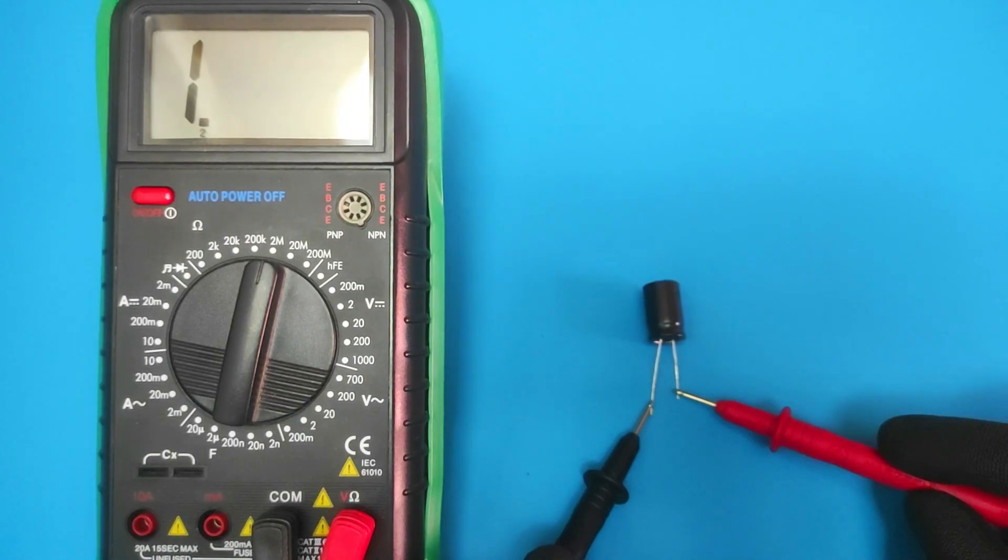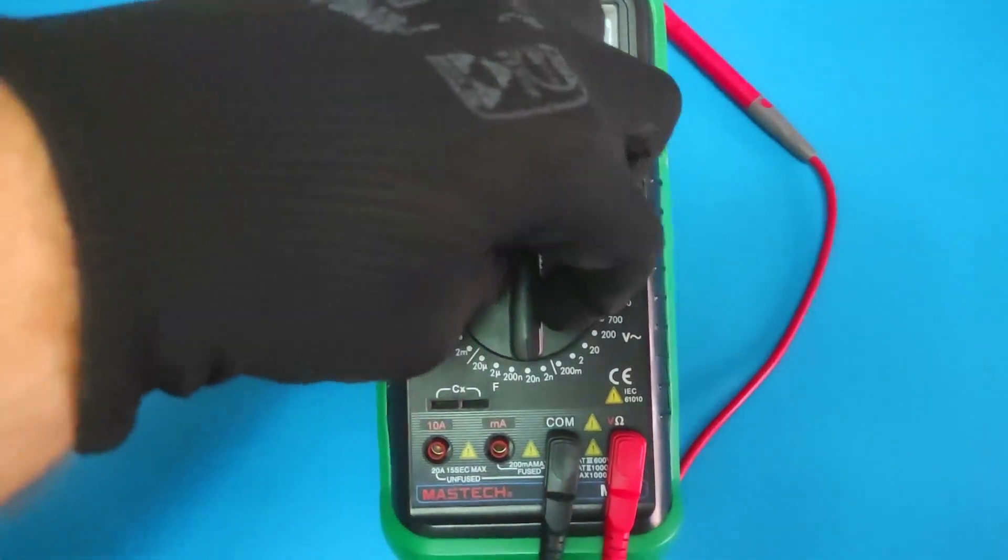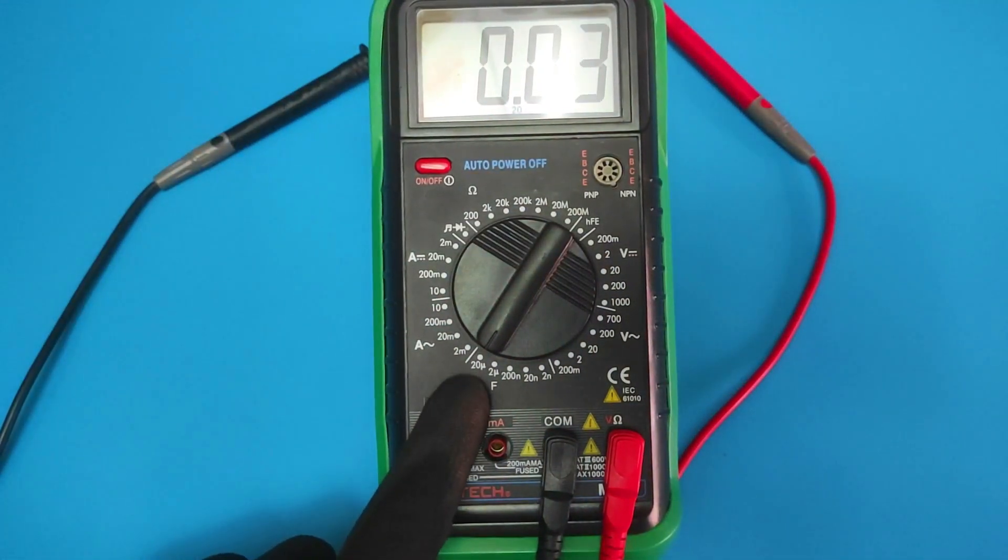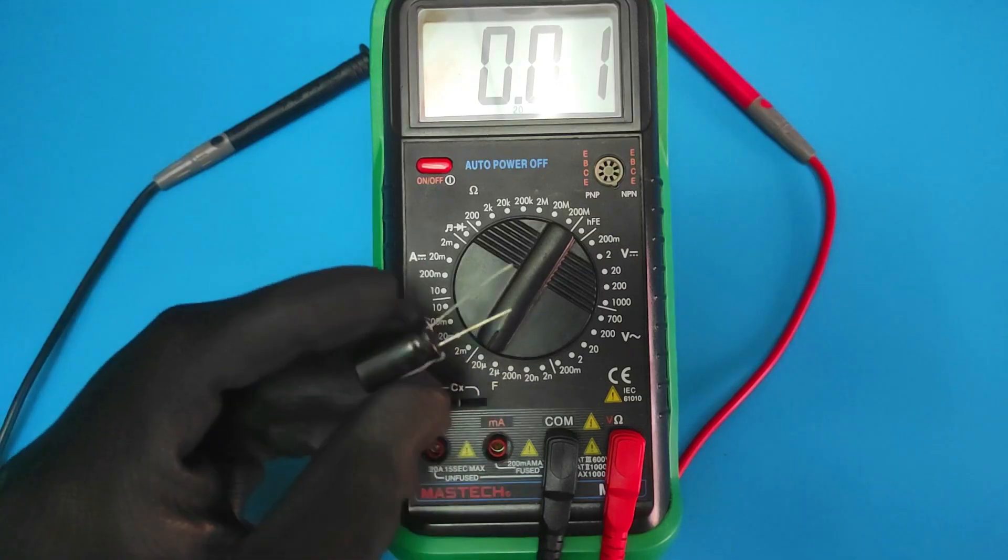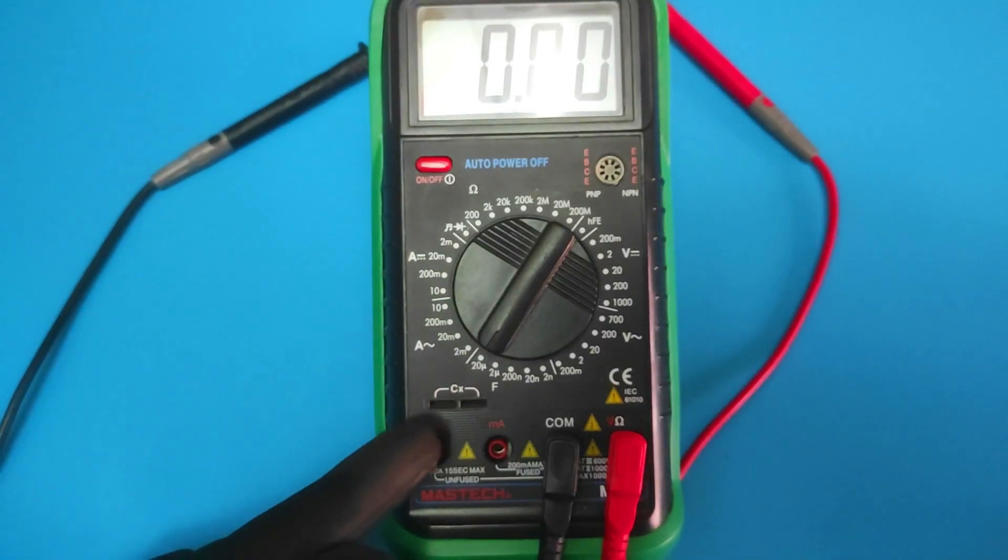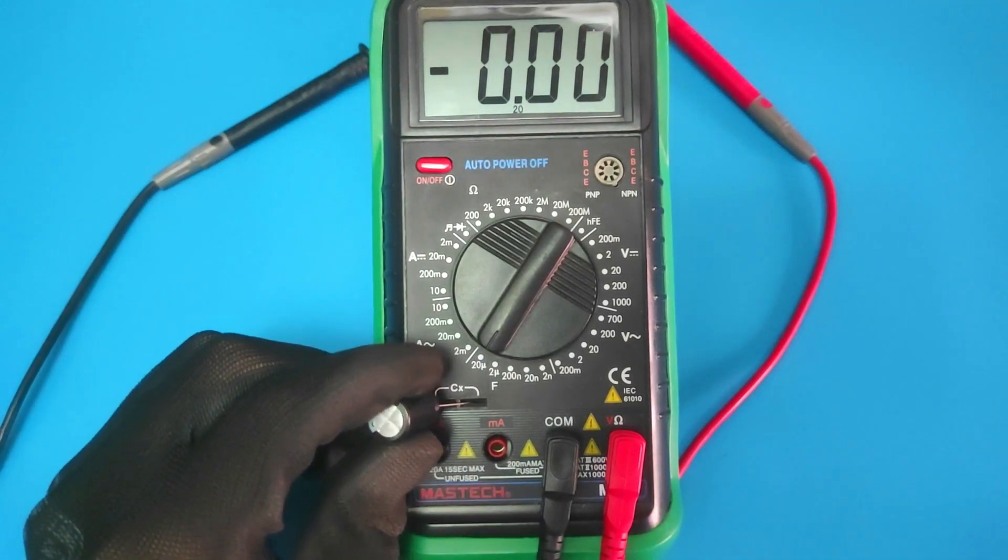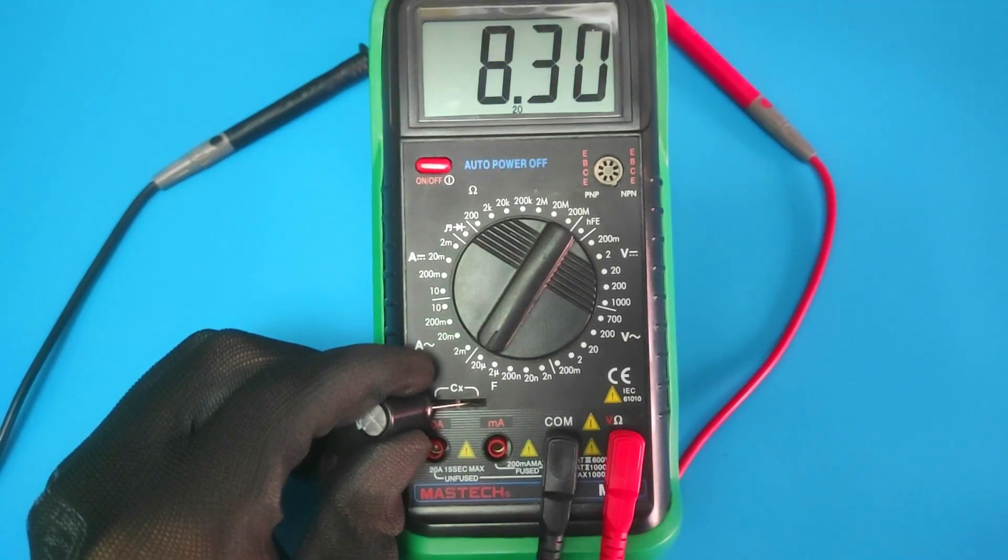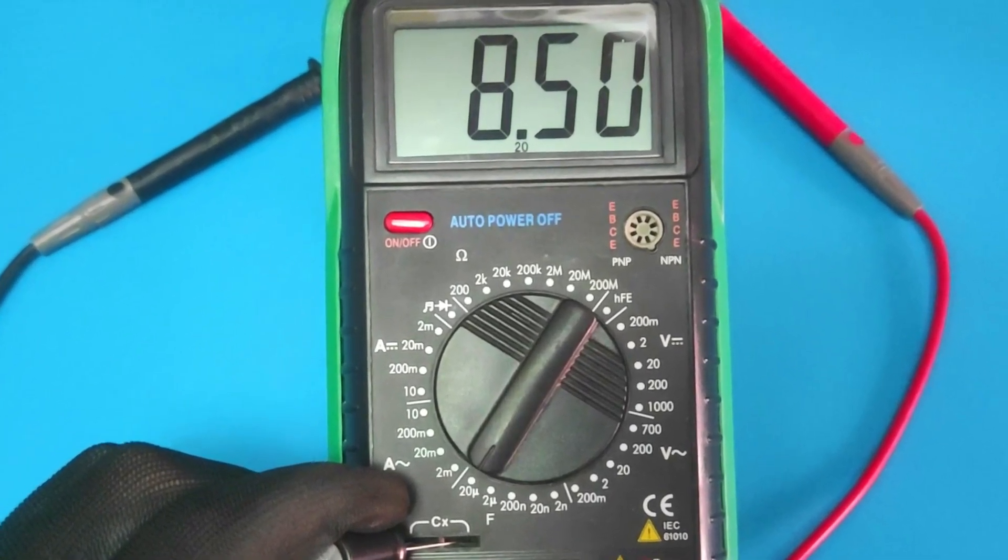Let's see the capacitance test. For the capacitance test, you need to set a larger capacitance value than the capacitor. This capacitor has a value of 10 microfarads, so we put 20 microfarads on the multimeter. And be sure to discharge the capacitor before this test. Simply connect the capacitor to the multimeter, and as we can see, the capacitance test is good.